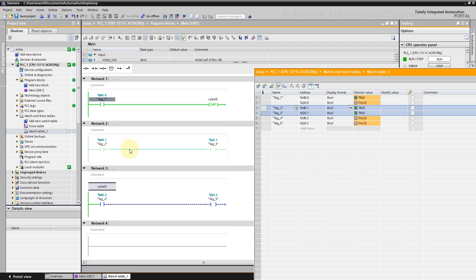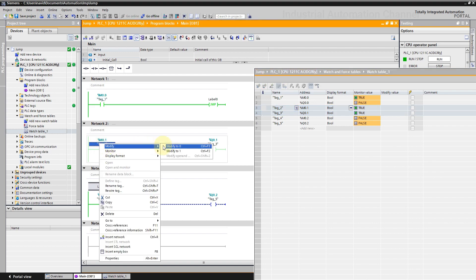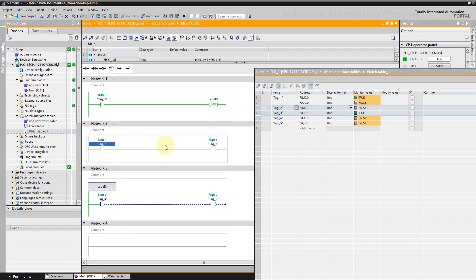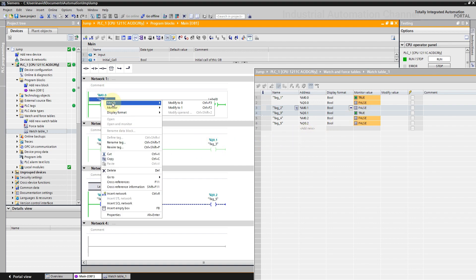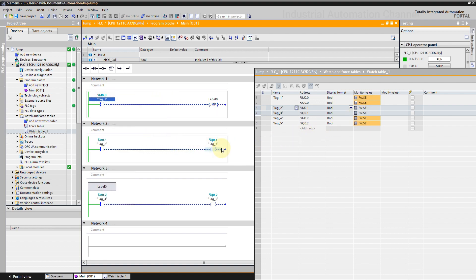But as I said this network is not executed anymore because of using jump operation. And we expected these variables to have a false value. But they are true. In this case, don't forget when we use jump, a network will not be executed. But the variables inside this network will hold their last state. That's an important point using jump instructions. If I modify m0.1 to 0, q0.1 will hold its last value, which is true. If I turn off the jump, now second network will be scanned again and the output will be off because the input is off. That is how jump works.